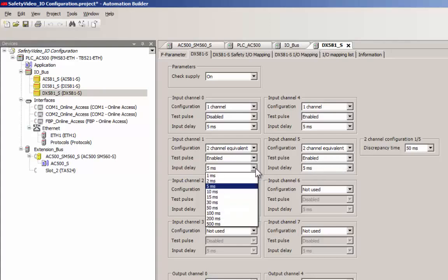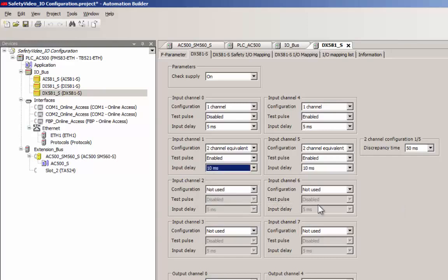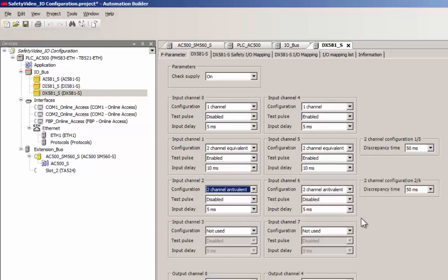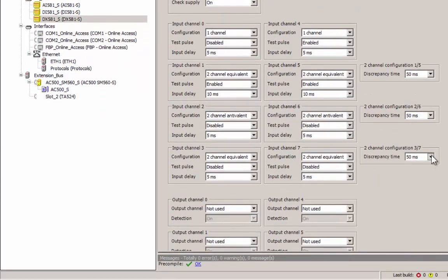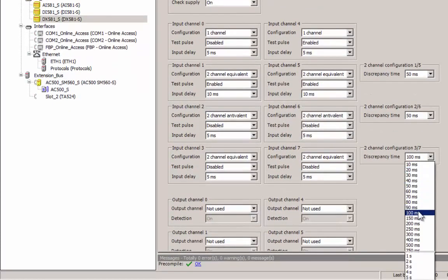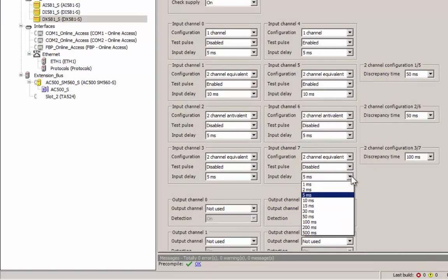Appropriate input delay value must be set according to the input device response time, in order to prevent channel passivation. Input delay setting acts like a low pass filter, to avoid frequent signal changes being sensed by the module.